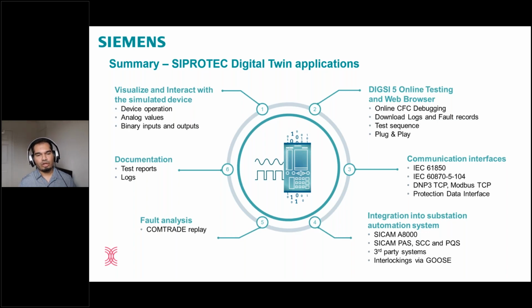Coming to number 5, you can do ComTrade analysis. So if a fault occurs at site, the field engineers will export the ComTrade file. They'll send it over to the engineer who has access to the digital twin. He will load the ComTrade file, having the same configuration of the relay at site. He'll be able to replay the fault and see what exactly is happening. Even if that engineer is far away from the site, he can test and validate using the digital twin what could be the issue and how to mitigate it.